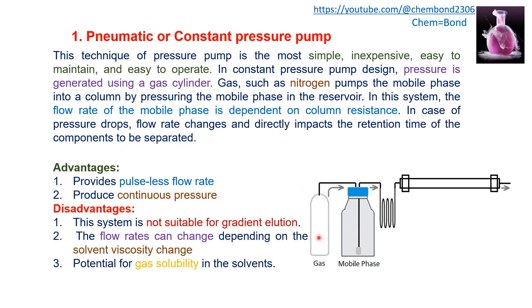If the pressure of the gas drops, the flow rate of the mobile phase changes and it will affect the retention time of the separated components. Advantages include pulseless flow rate and continuous pressure. Disadvantages include: not suitable for gradient elution, flow rate changes if solvent viscosity changes with temperature, and potential for gas solubility in solvents. If the gas is soluble in the solvent, the pressure will drop and affect the retention time of the component — this is the major drawback of this pump type.